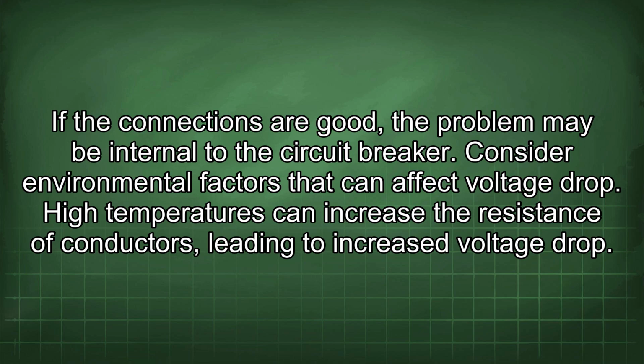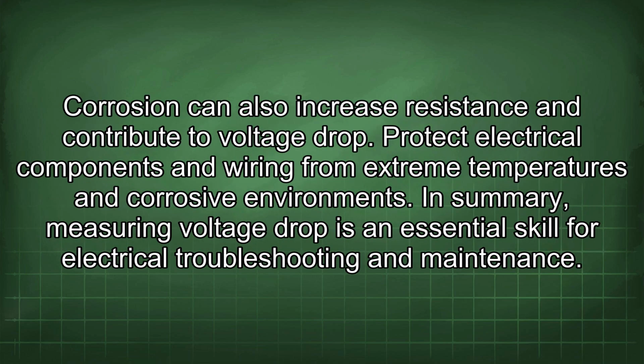Consider environmental factors that can affect voltage drop. High temperatures can increase the resistance of conductors, leading to increased voltage drop. Corrosion can also increase resistance and contribute to voltage drop. Protect electrical components and wiring from extreme temperatures and corrosive environments.